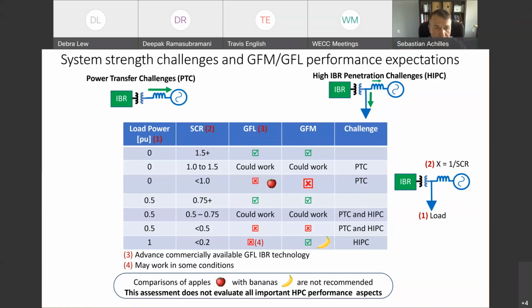If we then look to the next set of 3 rows with a load of 0.5 per unit, we see that with a short circuit ratio of 0.75 or higher, it's possible to get grid following to work. And this sounds like a contradiction. 0.75 is a very low number. We always say that the short circuit ratio required for grid following to work has to be 1.5, 1. Well, but when we make those statements, we're thinking about the system in the upper left.